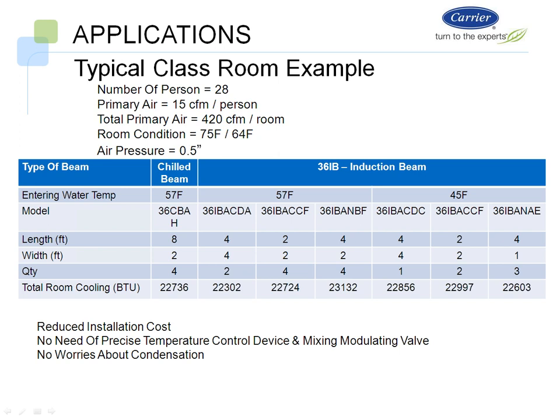It reduces your install cost because you're using fewer beams. So that means less outside air connections to units that I need. It means less mechanical piping or fitter work to the beams, as well as the install. If you look at it, a standard 2x2 unit of ours weighs about 40 pounds dry. That's typically a one-man install on a ladder, and it fits very neatly into a 2x2 type drop ceiling scenario. When you have an 8x2 device, there's no way, no matter how light or how heavy it is, it would ever be a one-man install.